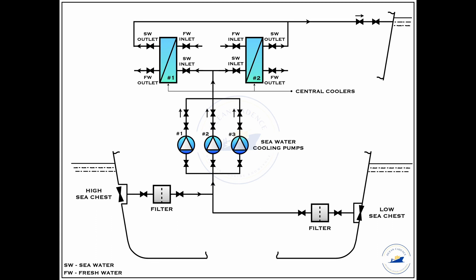Usually there would be a temperature gauge present for manual gauging of the temperature at the outlet line of the sea water that is being diverted from the coolers. This temperature would give us an idea of the temperature gradient with respect to the temperature of the sea water inlet that we are measuring from the filters, which is usually measured with the help of an infrared temperature measurement gun.